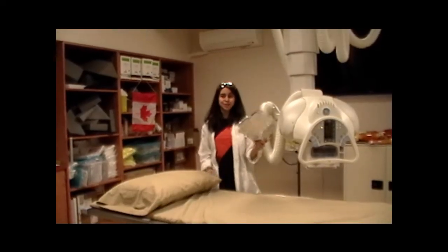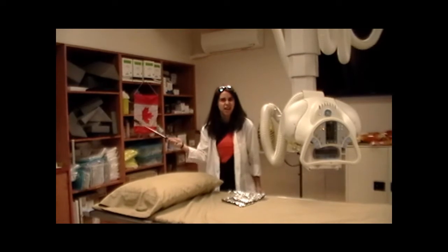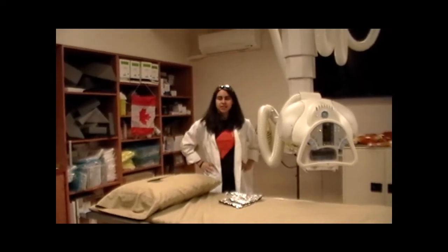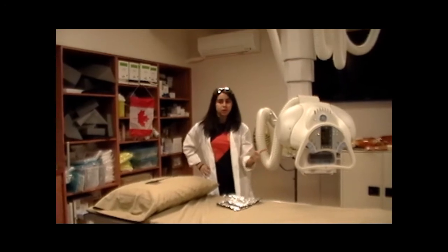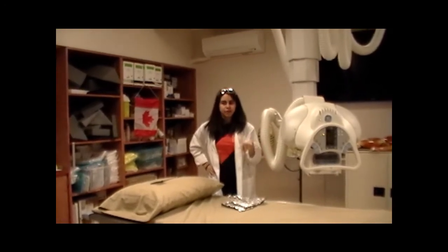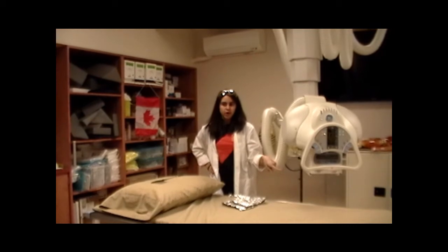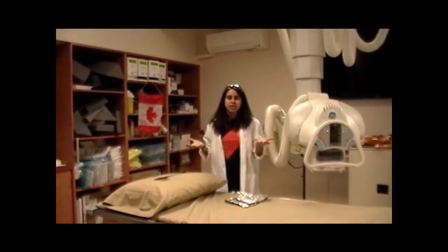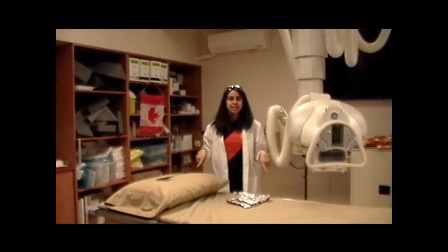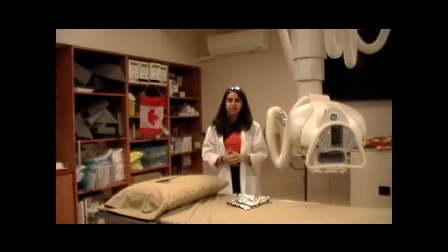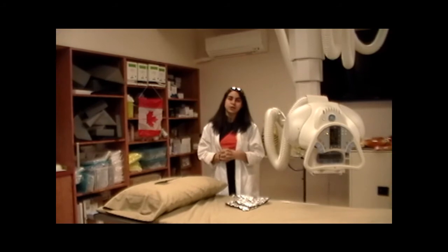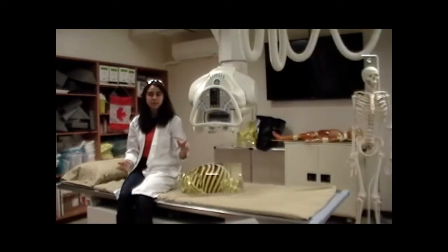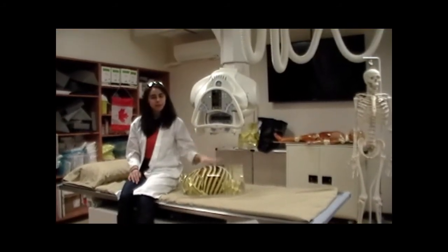This aluminum also accounts to get rid of that nasty scatter we saw earlier. The X-rays that transmit straight through without deflecting make for good image quality. Some of the X-rays get redirected, so they don't go straight through the body, making them end up elsewhere on the image. This lowers the image quality, since it doesn't accurately represent the anatomical part. This is what we call fog on the image, and it isn't useful. Scatter can come from the tube, or as seen before, from the patient.